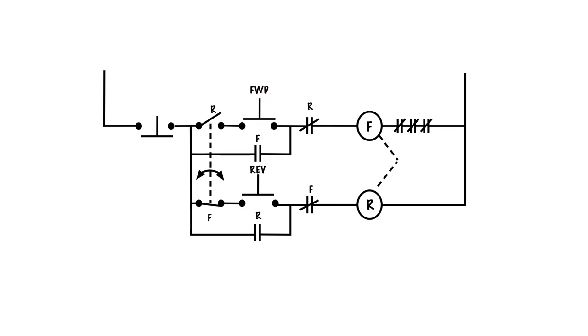But first off let's see what happens when this bounces back. My reverse button has gone back to its position, my stop button has gone back to its normally closed position and I still can't get the forward to go because as long as the motor is spinning through some sort of inertia in the reverse direction this zero speed switch will stay open. The moment it stops spinning this zero speed switch will close and then I can go ahead and hit forward.